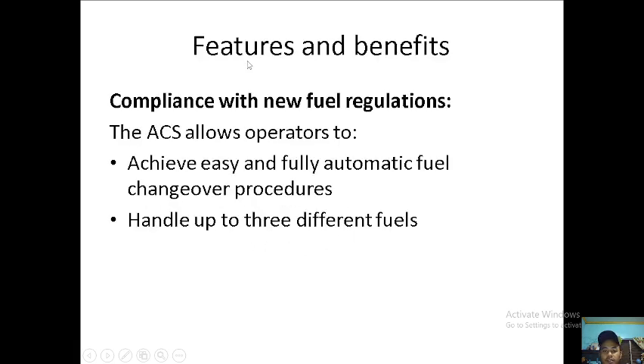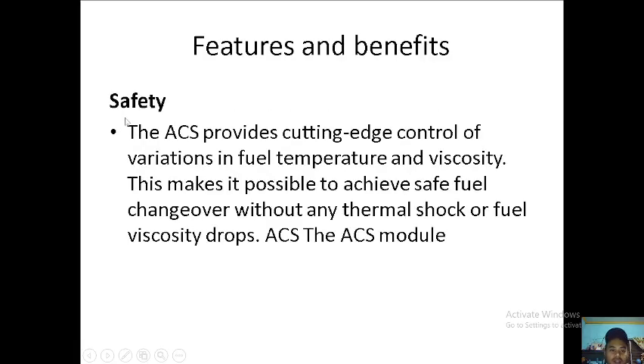So, features and benefits: compliance. It is in compliance with the new fuel regulations, achieves easy and fully automatic fuel changeover procedures, and handles up to 3 different fuels. So you can use HFO, DO, and another gas oil or gas fuel. For safety, it provides cutting-edge control of variations in fuel temperature and viscosity.